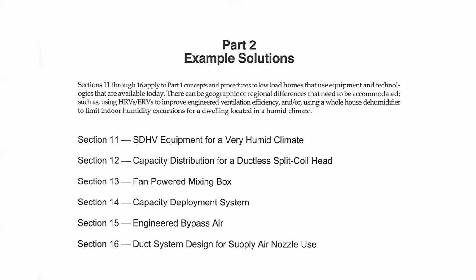For a dwelling located in a humid climate, one of the things that we kind of neglect when we do a design is that when we design a home, it's based on an average and not a peak. So we're always going to have temperature excursions, some pressure excursions inside the home, as well as humidity excursions. And we want to limit the humidity excursions the most, because that's what gives us our mold and mildew issues.